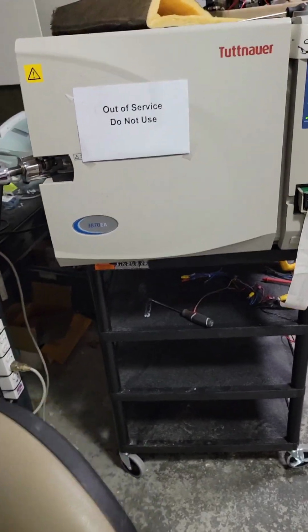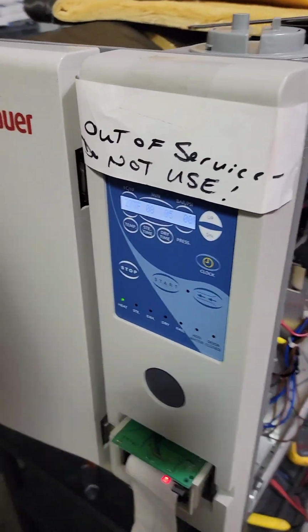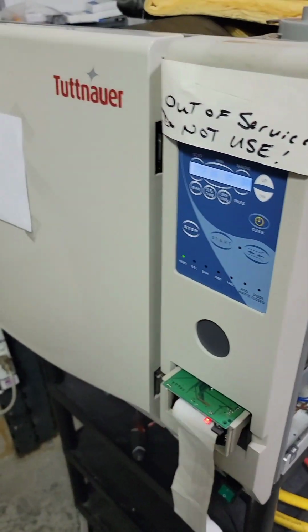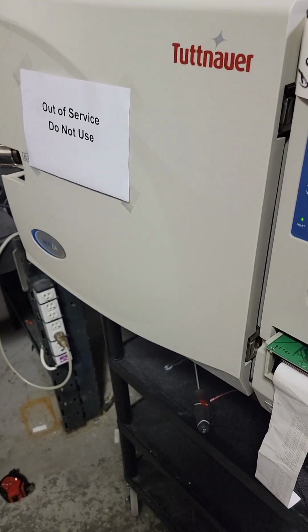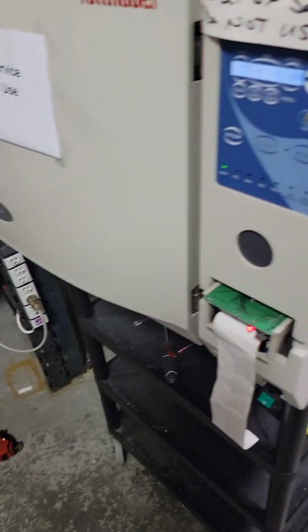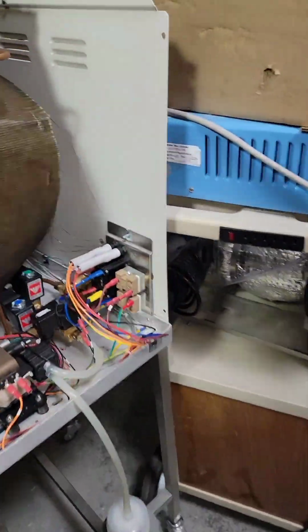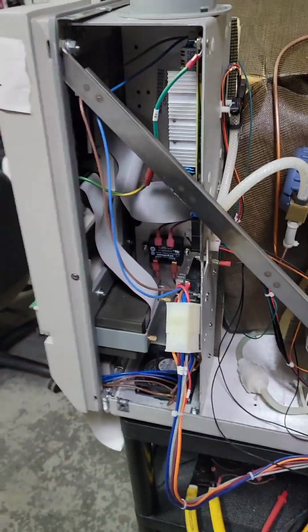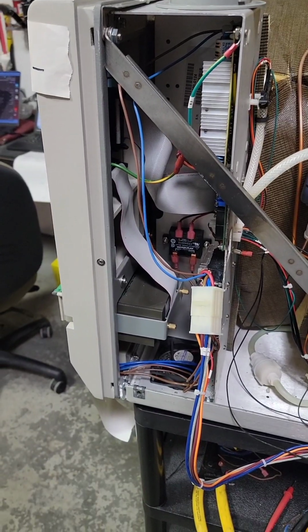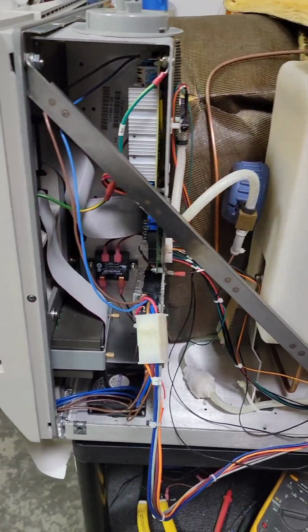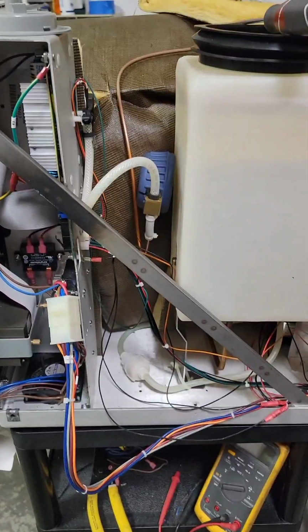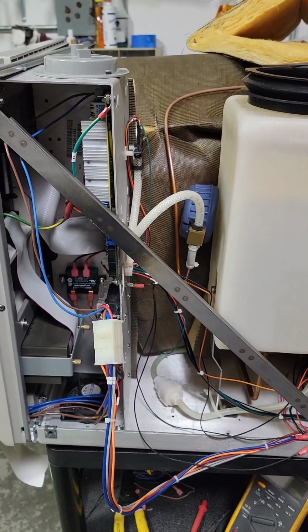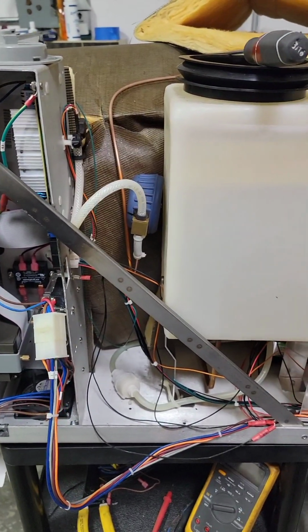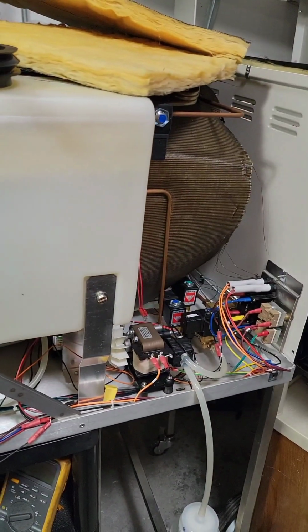I thought I made this video already, but I'm going to show you how we're going to calibrate a Tuttnauer sterilizer. The tabletops, whether it's an Easy 9, Easy 10, 3870, whatever, they're all the same calibration. So, first step, these units, the 3870s are all 230 volts. So make sure you're getting 230 within range of that. Because if you're plugged into a 110 outlet, you're going to have issues all over the place.